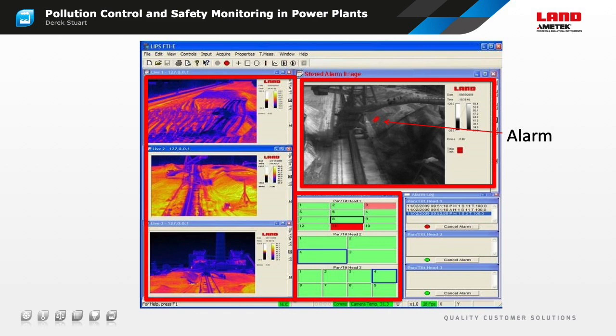Here is the display screen from a 3-imager system. In the left-hand panel, we see the live thermal image from each camera, with the color scheme chosen to give emphasis to the temperature range of interest. In the upper panel is an image showing an area of high temperature, highlighted. The bottom panel shows the patrol record for each of the imagers, with the status of the designated zones. The upper camera has a total of 12 zones of interest, the middle has 4, and the lower has 8. For each zone, green indicates no problem detected, pink shows that 1 pass found a problem, and red is an alarm condition triggered by 3 consecutive passes, each with a temperature above threshold.